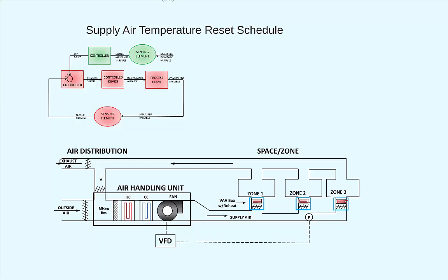So how exactly would we implement such a reset schedule? First off, let's define again what the issue is. Again, if all of the building is in heating mode, it doesn't make much sense to cool the air to 55 degrees Fahrenheit at the air handling unit just to heat it back up at the VAV boxes. So we could change the temperature set point for the air coming out of the air handling unit during such periods to minimize that waste. We could do that in one of two ways.